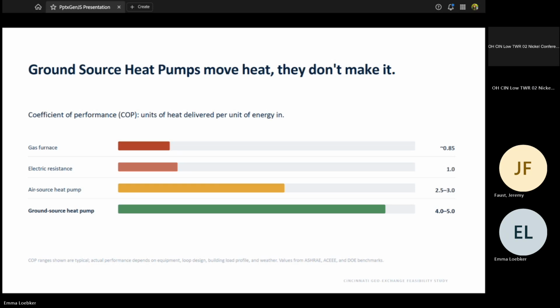For designers, this next slide shows how we evaluate different systems against one another using the coefficient of performance. Think of it this way: electrical resistance heating takes 1 unit of electricity in and produces 1 unit of heat out, a 1-to-1 ratio, which is our baseline. Air source heat pumps give a 2.5 to 3 times benefit over electric heating, while ground source heat pumps are 4 to 5 times more efficient.